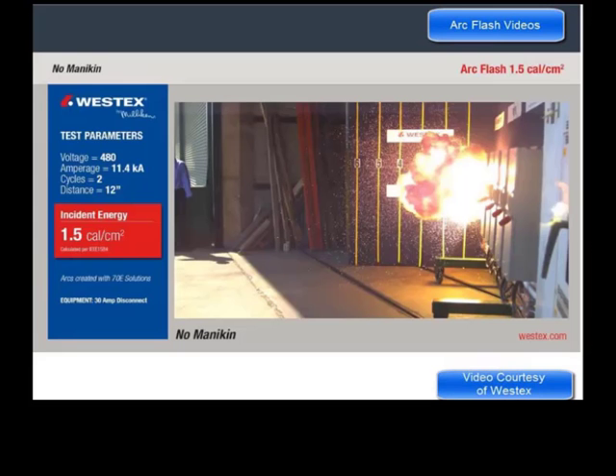This arc occurred in a 30 amp 480 volt disconnect. The incident energy is 1.5 calories per square centimeter, which could cause second-degree burns. The reaction time for the overcurrent protection device is 2 cycles, which represents 33 milliseconds. The arc flash event is almost instantaneous.